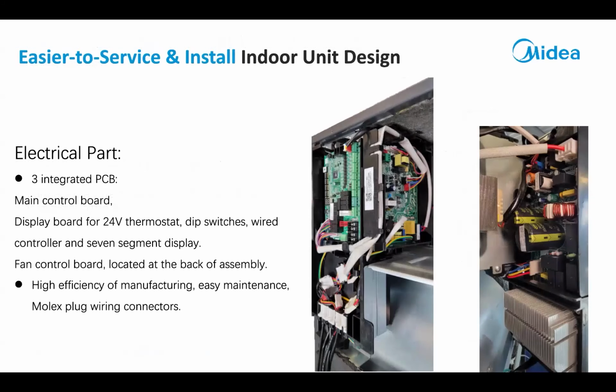Let's see, so there are 3 integrated PC boards in this thing. You have a display board, which they call a data conversion board. That's your 24-volt board. You have a main board, and then there's also a fan driver. The fan driver board is the one that is here on the right. Notice the heat sink. The heat sink is actually sitting directly in the airflow. This control box right here comes out with the removal of 3 screws.